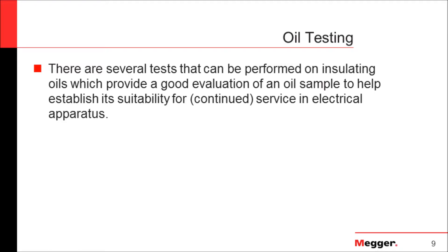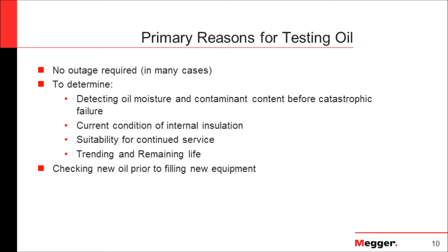Talking about oil testing, there are a number of different tests available that can be performed to check the condition of the oil and to see whether it would serve the remaining service life or if some corrective action is needed. Another advantage is that to perform testing on oil, the majority of the time I don't have to take the electrical apparatus offline. I can take an oil sample while the apparatus is energized and use that sample to perform tests to determine whether there is moisture or contamination present in the oil, or to find out what is the dielectric strength of the insulating oil.